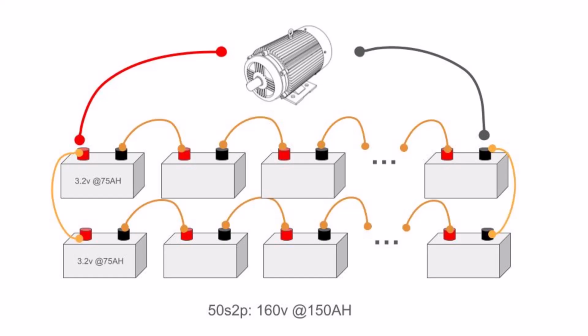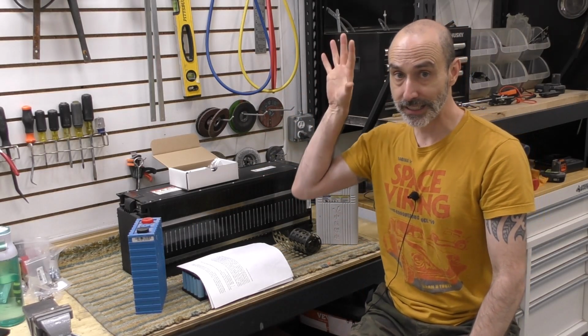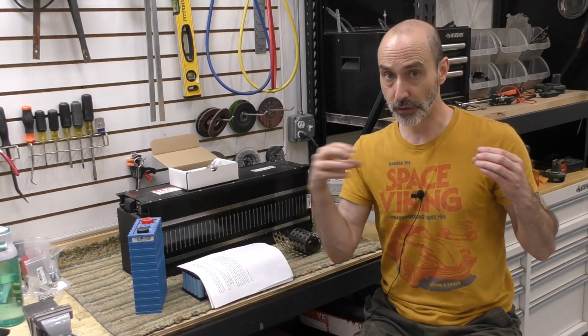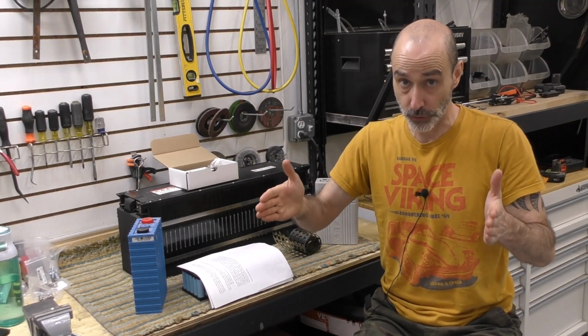If, let's say, there's a 0.2 volt difference, the moment I join those packs in parallel, current is going to immediately flow from the higher voltage pack to the lower voltage one, because it has to balance itself. That current could be substantial at 160 or 180 volts. If I was a couple tenths of a volt off, and I put that final bus bar on without wearing gloves, I could have 100 amps suddenly travel through that bus bar the moment I connect it. So there's a bit of danger in connecting high voltage packs in series and then paralleling those large voltage series packs.